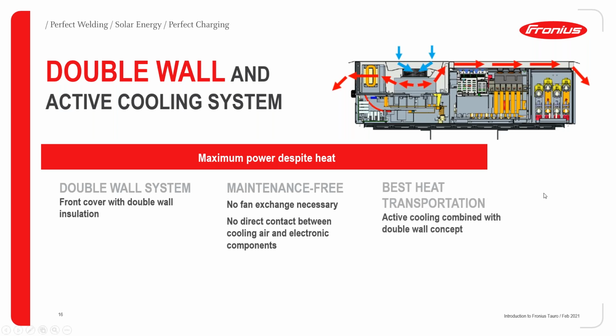And then Fronius always believes in active cooling technology. Now this active cooling combined with the double wall, it's the best heat transportation we have seen in the market. So this inverter has fullest performance up to 50 degrees Celsius. And then from 50 degrees, there will be a power derating. Please pay close attention to our data sheet where you can read more about this power derating after 50 degrees.